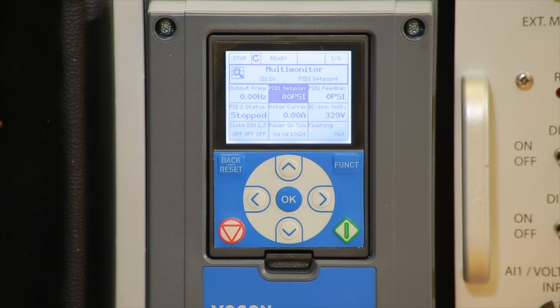This timer can be any number of seconds that you like. But we want to know when the pressure is too high, when the drive is no longer needed. After a few seconds, the drive will go to sleep, and we're going to demonstrate this shortly. So the speed is slowing down, 39 Hertz. Minimum speed, I believe, for this application is 30 Hertz. So at 35, it went down, so the timer now starts counting. And then we're going to put the drive to sleep shortly here. Here, the drive is asleep.